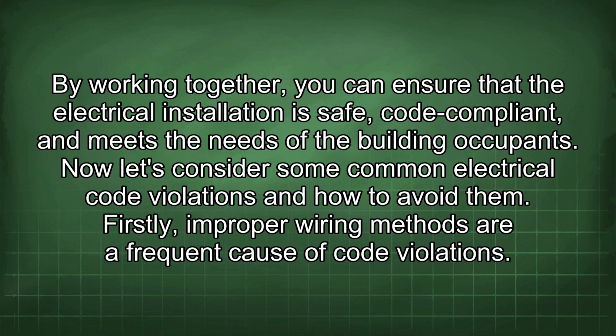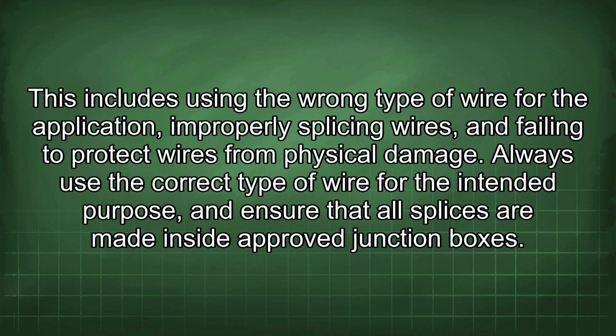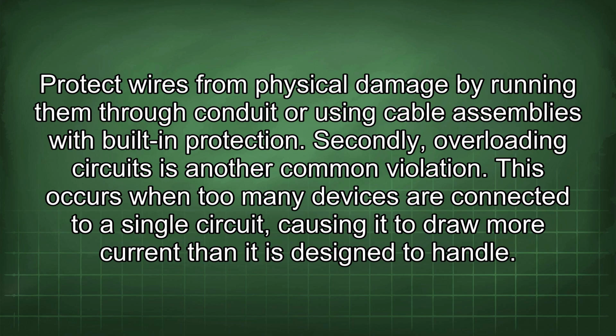Firstly, improper wiring methods are a frequent cause of code violations. This includes using the wrong type of wire for the application, improperly splicing wires, and failing to protect wires from physical damage. Always use the correct type of wire for the intended purpose, and ensure that all splices are made inside approved junction boxes. Protect wires from physical damage by running them through conduit or using cable assemblies with built-in protection. Secondly, overloading circuits is another common violation.